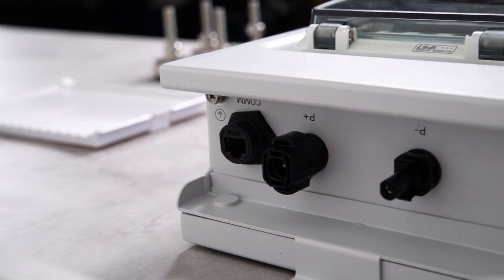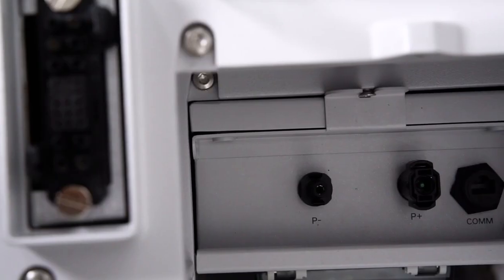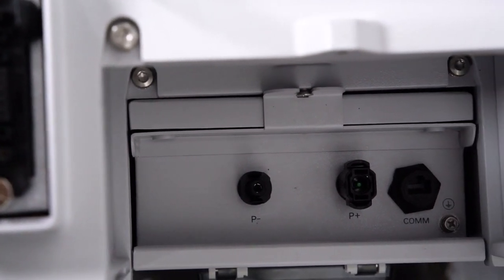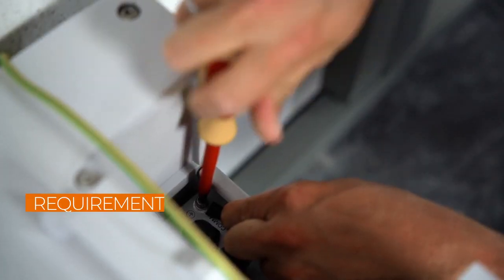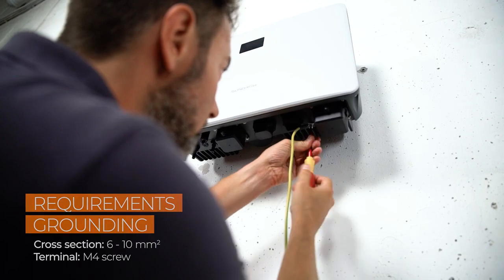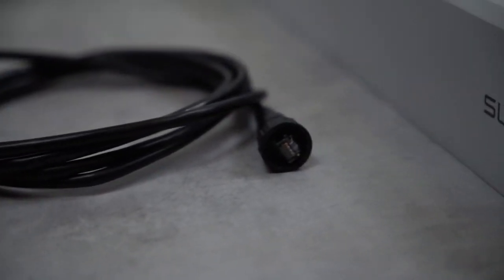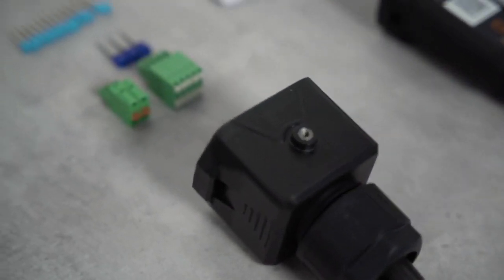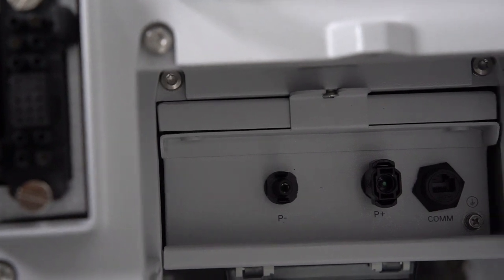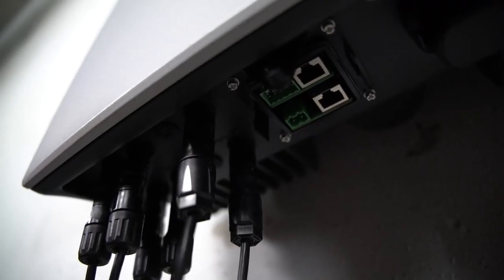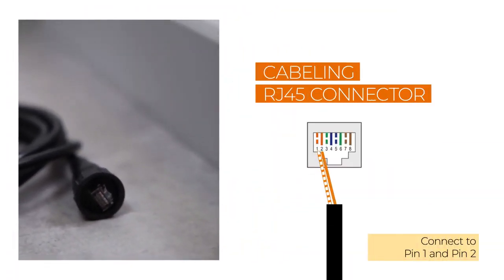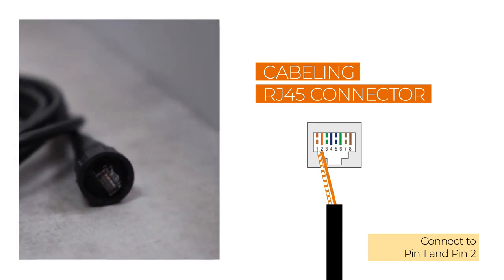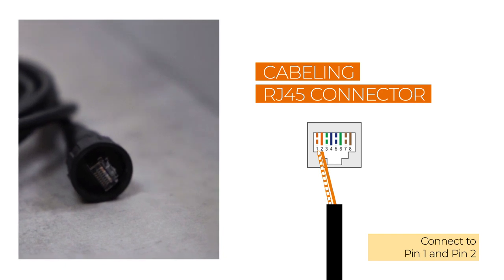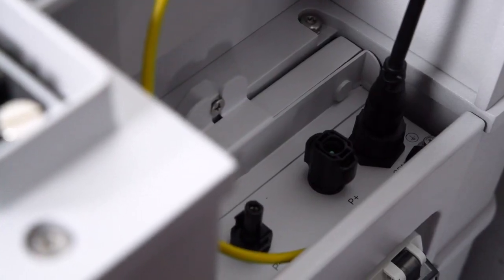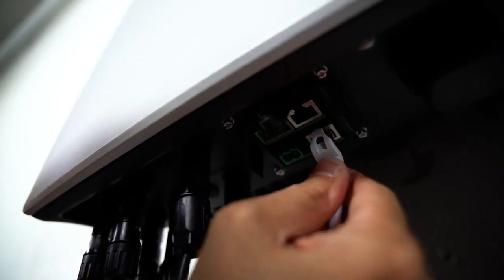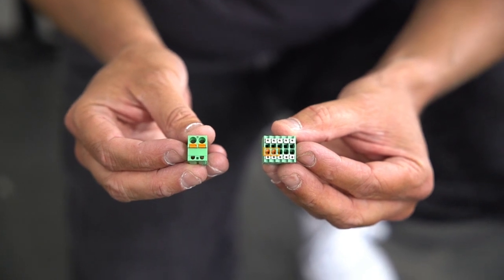Now let's come to cabling. The battery has 4 connectors: grounding, P+, P-, and one terminal for communication with the hybrid inverter. Let's start with the grounding. Fix it on the battery side and connect it to the ground at the bottom of the inverter. In the next step, the battery needs to be connected to the communication plug of the single-phase hybrid. The sealed RJ45 connector is part of the delivery scope. Simply connect it to your cable. The white-orange cable of the communication cable is connected to pin 1 and the orange cable to pin 2 on the RJ45 connector for the battery side. Connect the communication cable to the battery. The other end of the cable can be connected to the single-phase hybrid via Ethernet or via the pins 2 and 4 of the communication plug.